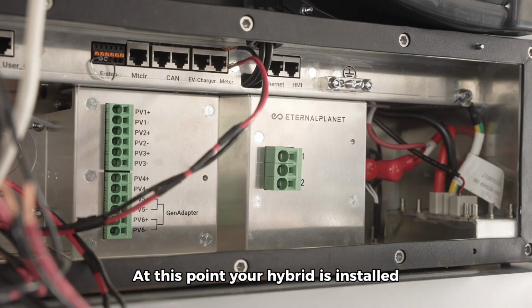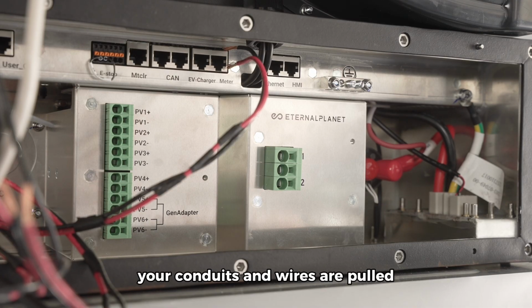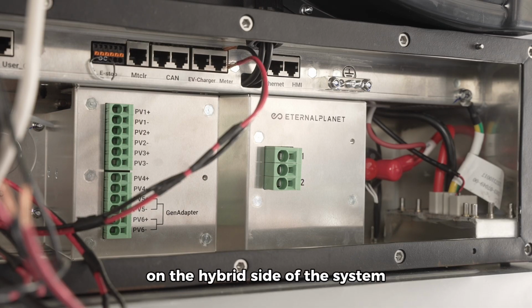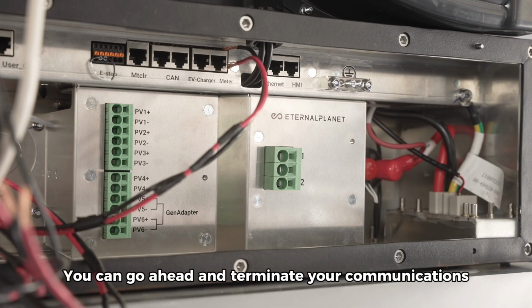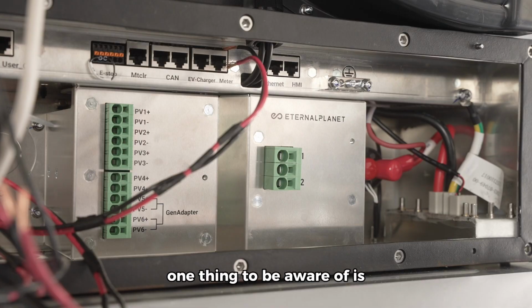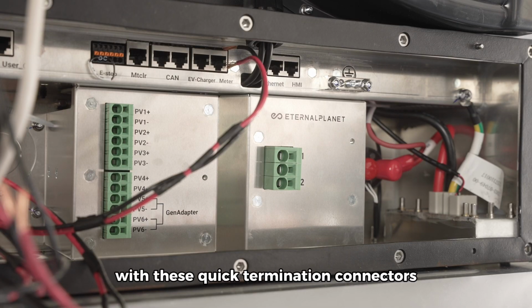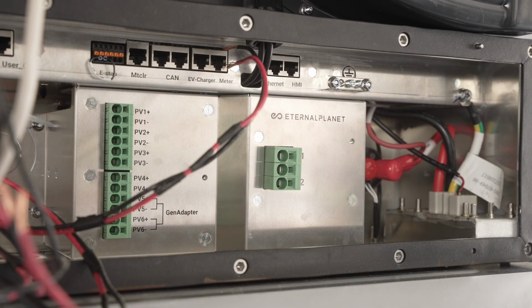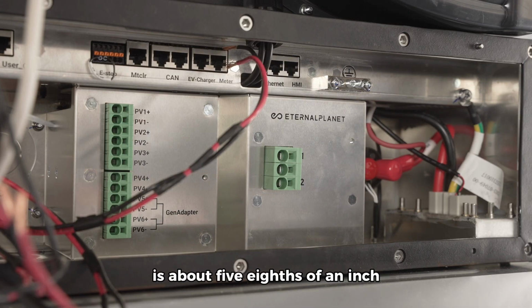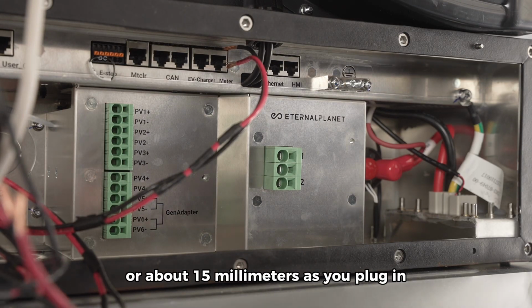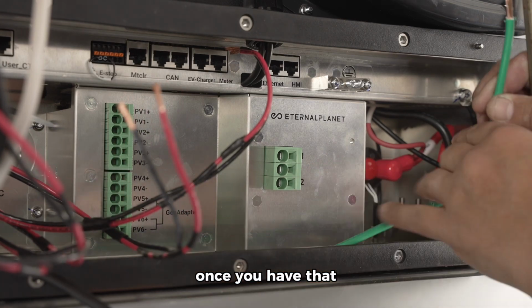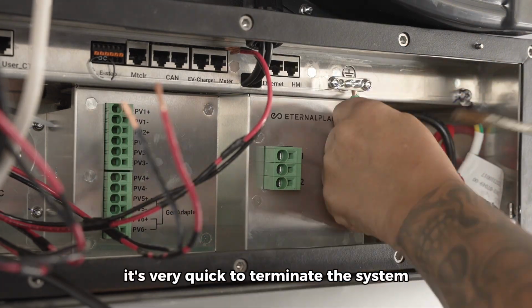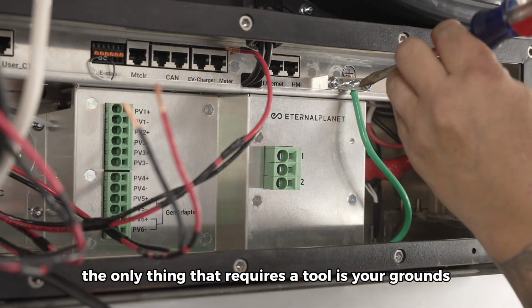At this point, your hybrid is installed, your conduits and wires are pulled, and you're ready to terminate on the hybrid side of the system. You can go ahead and terminate your communications, your grounds, or whatever is most convenient. One thing to be aware of is with these quick termination connectors, you want to make sure your stripping length is about 5/8 of an inch or about 15mm as you plug in. Once you have that, it's very quick to terminate the system. The only thing that requires a tool is your grounds.